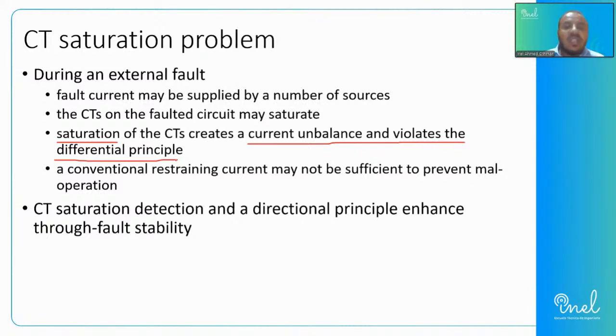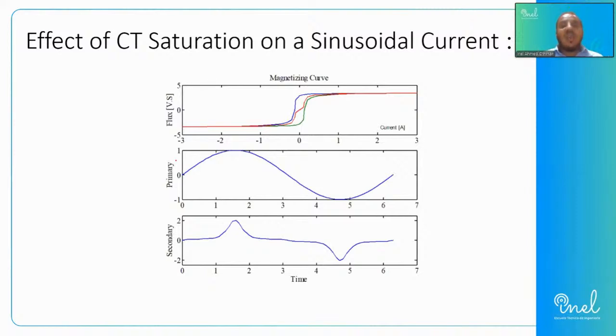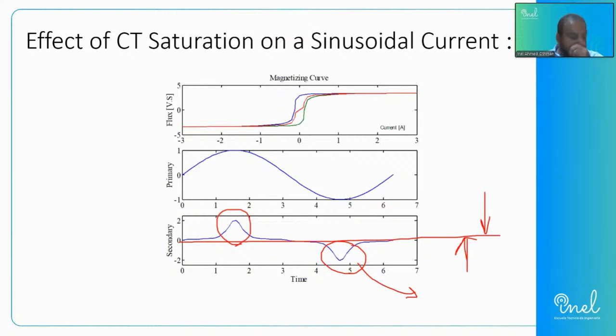And that's why we should detect and handle any CT saturation to confirm our differential protection is working properly. At least we are securing the stability of our protection scheme. And here are some curves which confirm that in case we have some saturation, there is some differential. Usually, in normal conditions, our difference should be around 0, except if there is some saturation, we may face some differential component which leads to maloperation and false tripping of our differential protection.